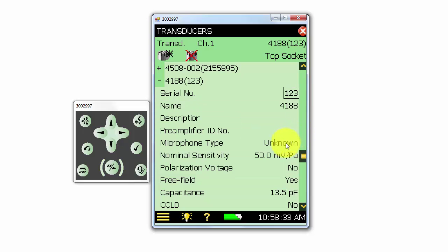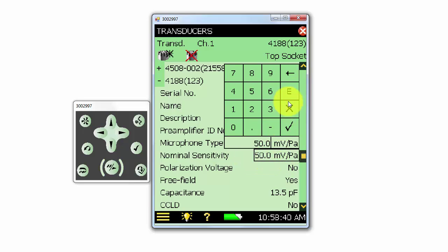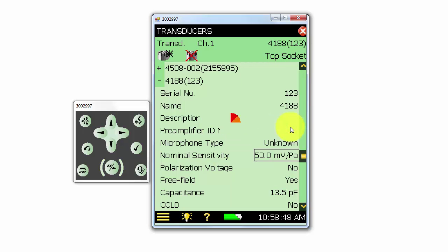Next, we'll want to make sure that the nominal sensitivity entered matches the appropriate nominal sensitivity for the microphone type. 4188s have a nominal sensitivity of 31.6 millivolts per pascal, so that's what I'll enter under the nominal sensitivity. 4188s are pre-polarized, so I'll leave the polarization voltage set to no.